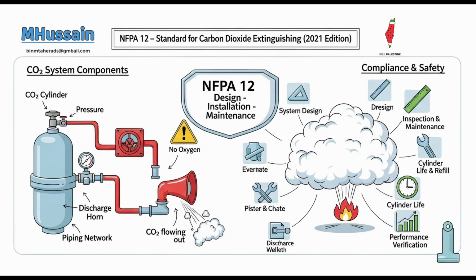So, if the alternatives are also dangerous in that specific situation. Precisely. This means CO2 is chosen only when other, safer gaseous agents simply can't achieve the required fire suppression without creating unacceptable health risks. Makes sense. What else? Another exception is for fires involving energized electrical equipment greater than 400 volts in grouped electrical cables. High voltage again? Especially where no gaseous alternative agent has been successfully tested to prove its effectiveness for such specialized high-voltage hazards. They're also permitted when current design methods or hardware for handling unenclosable openings or ensuring extended discharge aren't available for other gaseous agents. So technical limitations of alternatives. Leaving CO2 as the most practical choice.